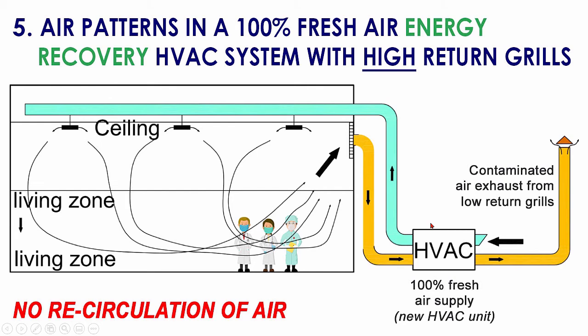Here we can see again that the fresh air unit is in the system, but here the fresh air unit replaced the traditional HVAC system or the HVAC unit. Here we can see the fresh air coming in and is cooled or heated by the 100% fresh air unit, and then it moves toward the ceiling diffuser. From the ceiling diffuser, the 100% fresh air is dropped into the living space. And as a lot of fresh air is dropped into the living space, the contaminated air in the living space is getting diluted at a high level. And the level of contamination is very low because of the dilution of the air.